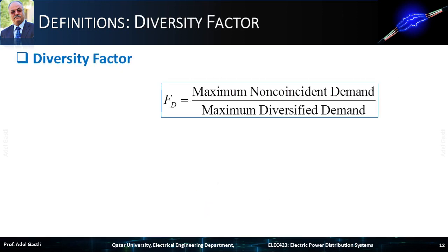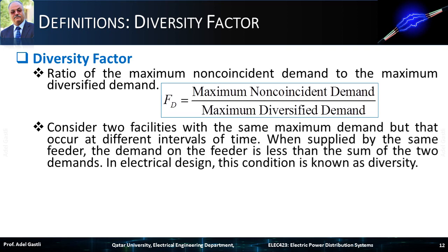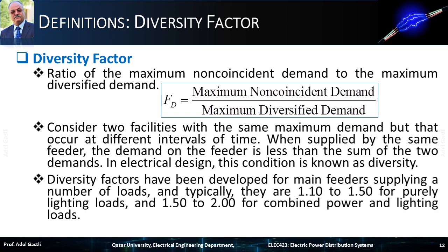Next, we will define the diversity factor. It is the ratio of the maximum non-coincident demand to the maximum diversified demand. For instance, consider two facilities with the same maximum demand but occurring at different intervals of time. When supplied by the same feeder, the demand on the feeder is less than the sum of the two demands — in electrical design, this condition is known as diversity. Diversity factors for main feeders are typically 1.1 to 1.5 for purely lighting loads, and 1.5 to 2 for combined power and lighting loads.